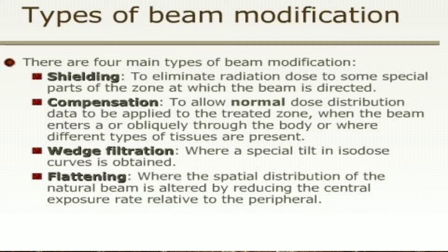In shielding, we use to eliminate radiation dose to some special parts of the zone at which the beam is directed. Compensation is used to allow normal dose distribution data to be applied to the treated zone when the beam enters through the body or where different types of tissues are present. In wedge filtration, a special tilt in isodose curve is obtained, and in flattening, the spatial distribution of the natural beam is altered by reducing the central exposure rate related to the peripheral.